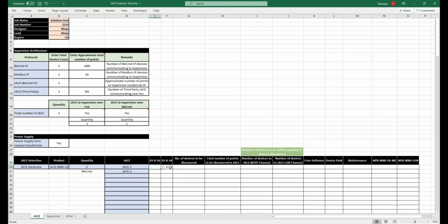The requirement here is you have to input the number of IO16s first. You cannot go the other way around, taking IO34s to whatever number you want and then coming back to IO16. It has to be sequential with IO16. Let's consider 2 numbers of IO16 I can have, and I can have a maximum of 7 numbers in IO34. So I'm going to select 2 of these and 2 of these for now.